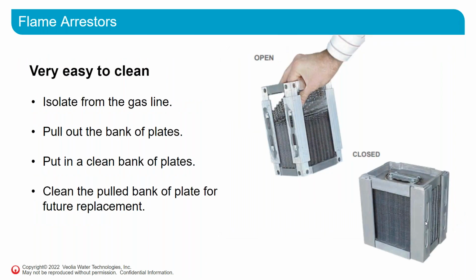Typically, we include redundancy. You can see 2 in that picture on the previous slide, so that you can work on one while still having one in service. And they're installed, especially in lines to those relief valves and also to the flare. They're very easy to clean. You can pull out the box and basically spray it with a hose. If you happen to have scaling on it, you can probably use a pressure washer for most buildup. You might need to use some kind of acid cleaning. Again, the manufacturer's instructions should include what to do if you see scaling.